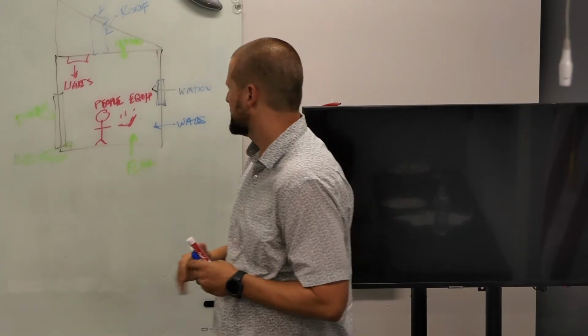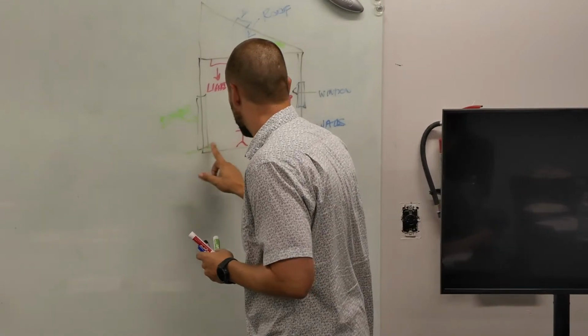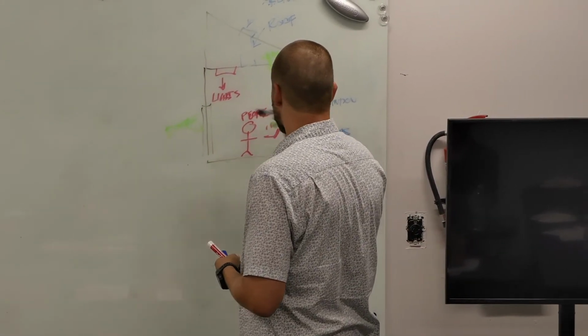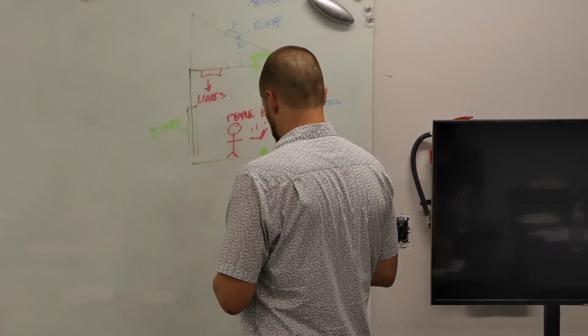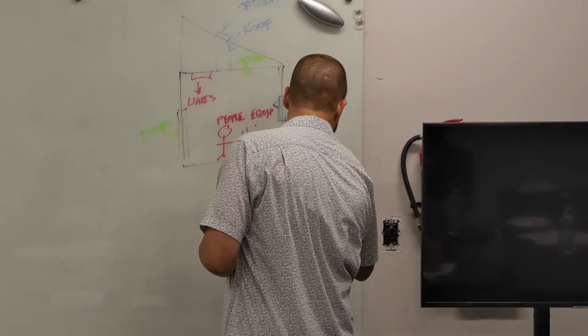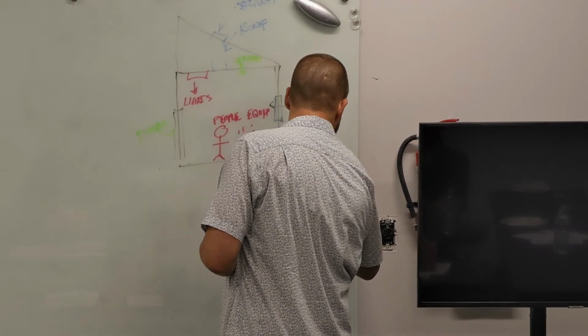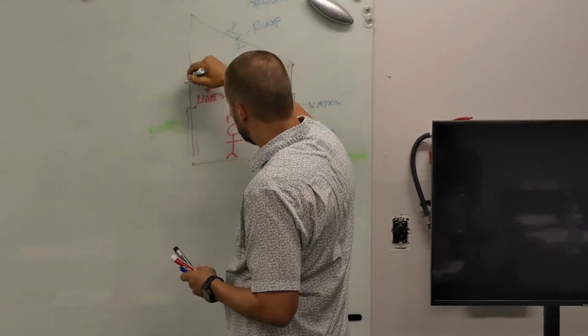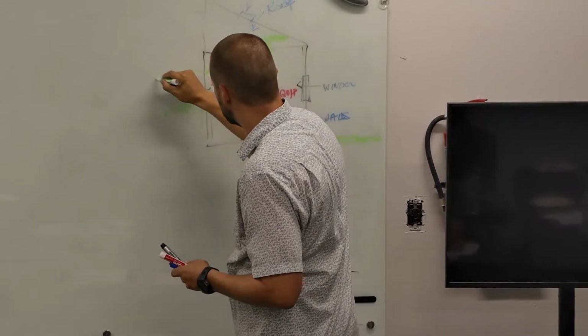And actually, I'm going to draw infiltration not here, because this is different. This is an exterior wall, and this is an interior wall or a partition. So if there's a temperature difference between partitions, we have a partition load.